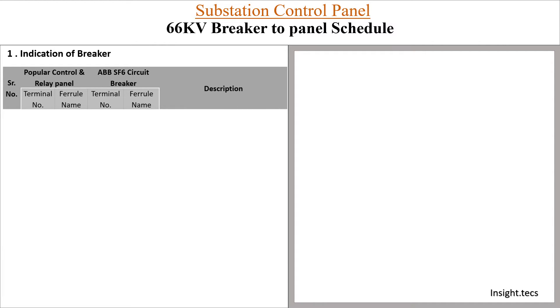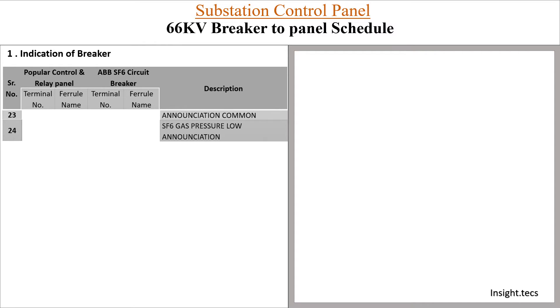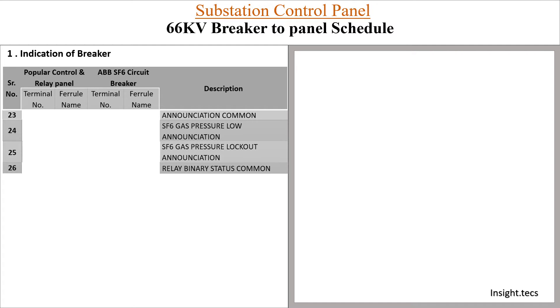Now let's start the schedule for the annunciation circuit and giving digital inputs to the digital relay. What we will need for the annunciation circuit: annunciation common, SF6 gas pressure low annunciation. Whenever the SF6 gas is lower than specified limits for the breaker, there will be a lockout. So we have to give annunciation for SF6 gas pressure lockout. Then we will start about digital relay inputs — we will need a common for that, then input of SF6 gas lockout and CB open status. According to the requirement of relays, you can take many other inputs as required.